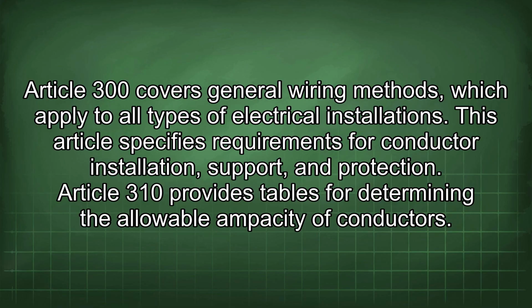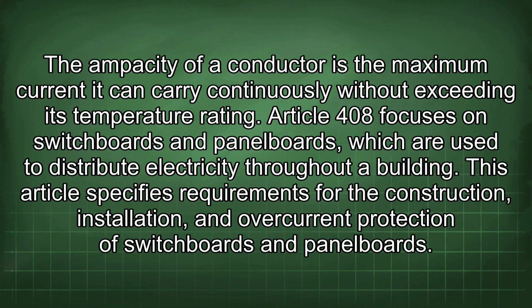Article 310 provides tables for determining the allowable ampacity of conductors. The ampacity of a conductor is the maximum current it can carry continuously without exceeding its temperature rating. Article 408 focuses on switchboards and panel boards, which are used to distribute electricity throughout a building. This article specifies requirements for the construction, installation, and overcurrent protection of switchboards and panel boards.